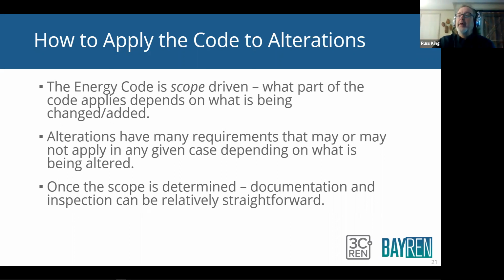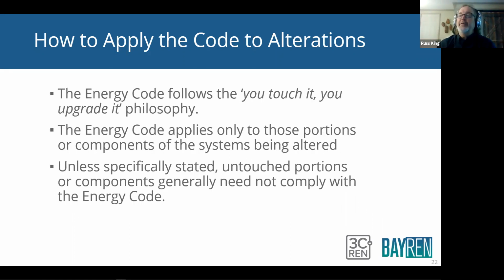That's very important. All right, so the energy code follows the "you touch it, you upgrade it" philosophy. The energy code applies only to those portions or components of the system being altered. Unless specifically stated, untouched portions or components generally need not comply with the energy code. All right, there are a couple of little things where you're not necessarily touching something, but the code does trigger a change to it. The best example of that is if you replace a rooftop package unit. Okay, that's all you're doing. It's replacing the rooftop package unit. You're taking the other one off, setting a new one on there.